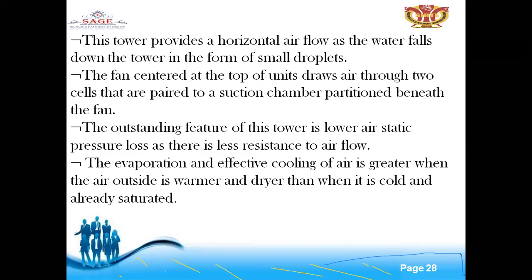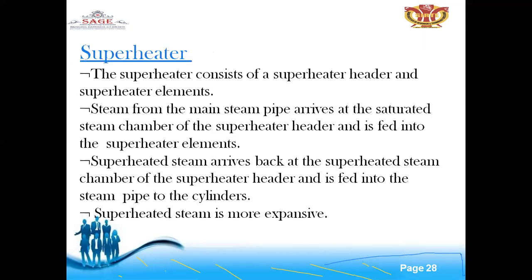The outstanding feature of this tower is lower air static pressure loss, as there is less resistance to the airflow. The evaporation and the effective cooling of air is greater when the air outside is warmer and drier than when it is cold and already saturated.